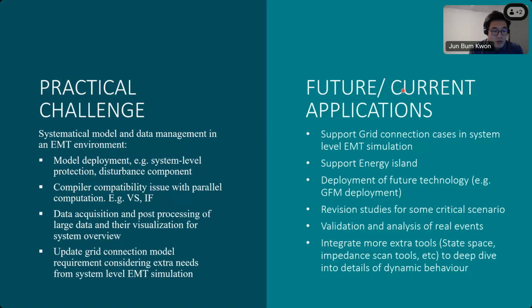And updating the grid connection model requirement considering extra needs from system level EMT simulations — we typically mention compiler versions and PSCAD versions, and the model should comply with all our grid connection requirements. But if you would like to enable features like system EMT level based validations in connection with the grid connection process, then we need to define several extra efforts.